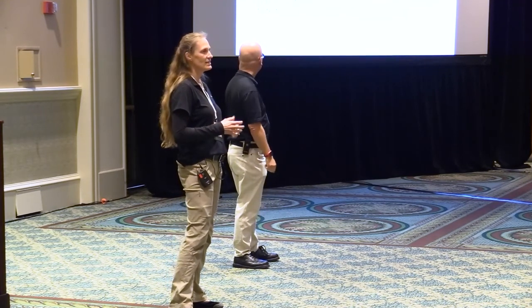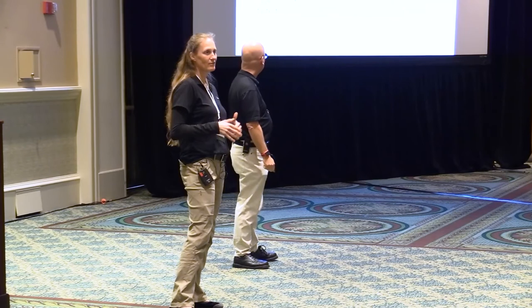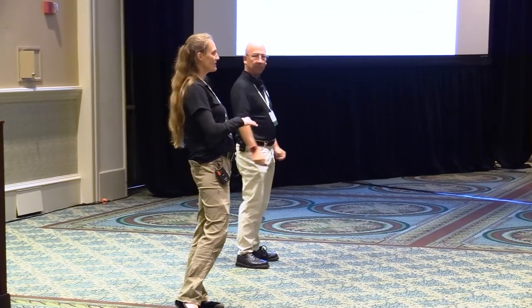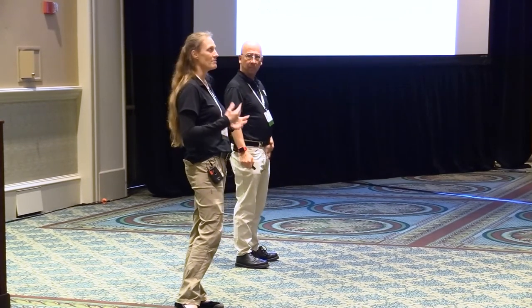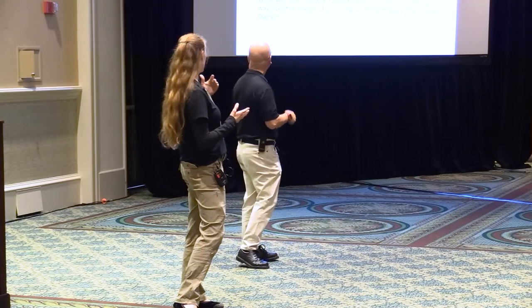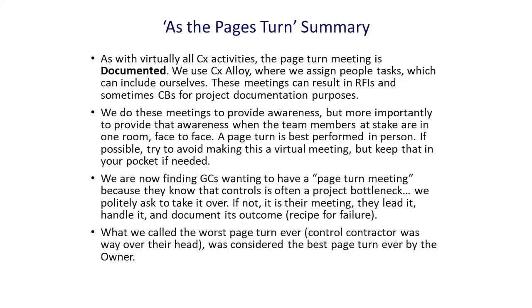Right. We oftentimes see these meetings lasting 2 to 3 hours. And if the building is more complex or you have more complex systems, they can be 2, 3, 4 meetings. And they don't just necessarily apply to controls. You can have a lot of value just doing a fire alarm controls page turn or security, like everything else with commissioning, right? And we want to be documenting this. So it's really important that it is documented.